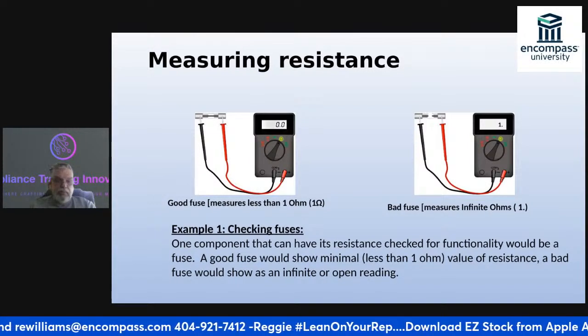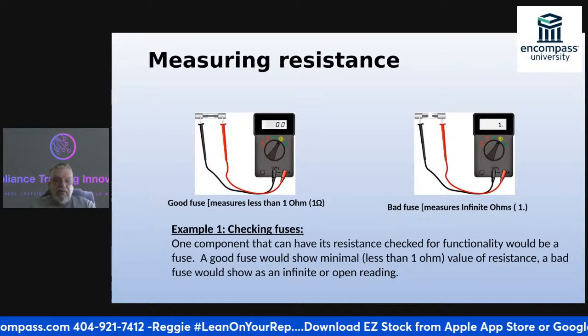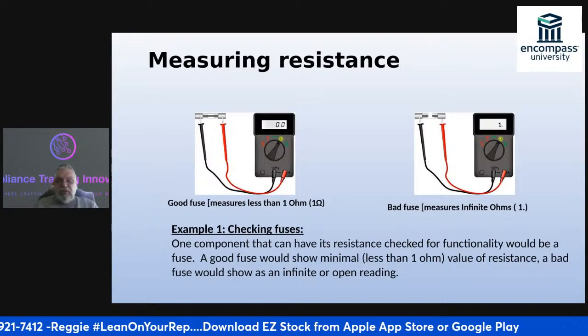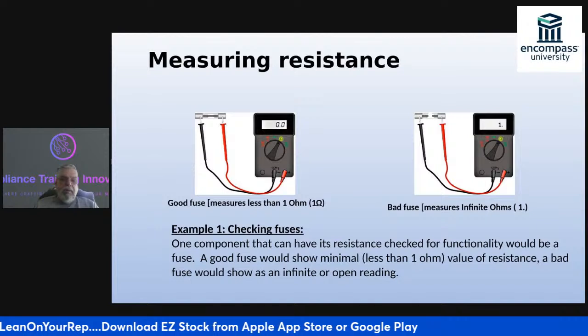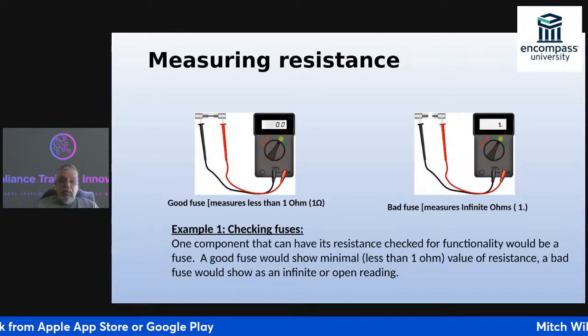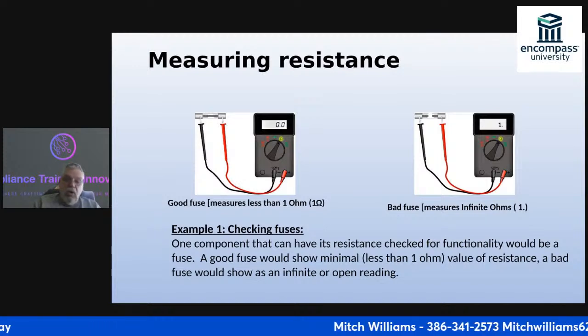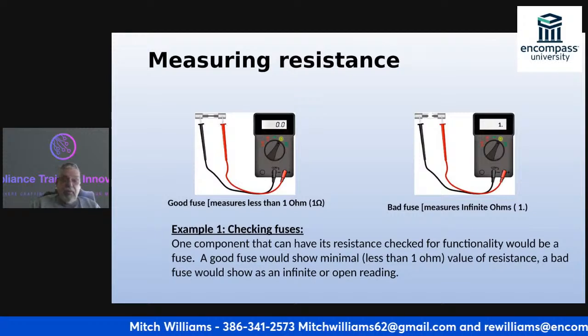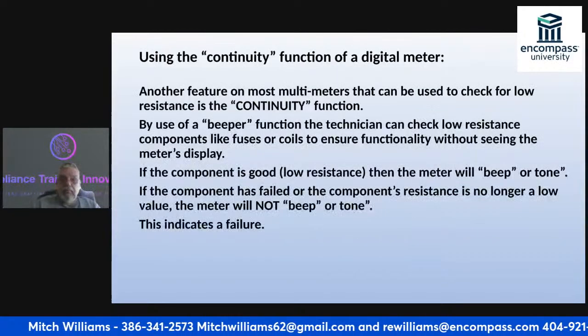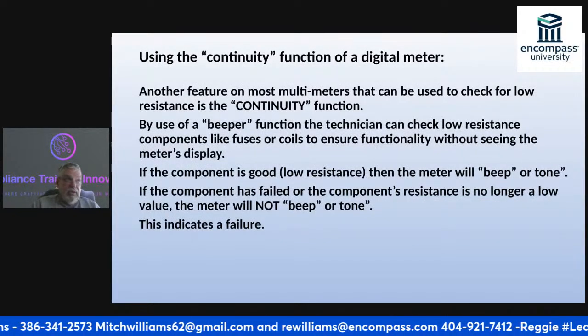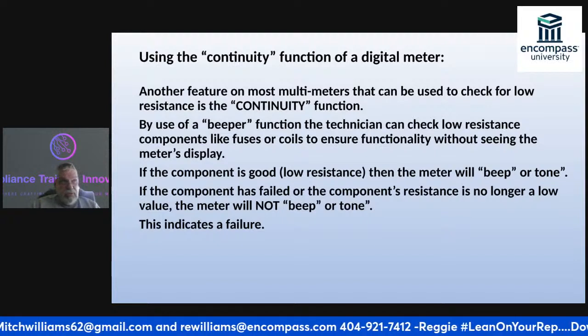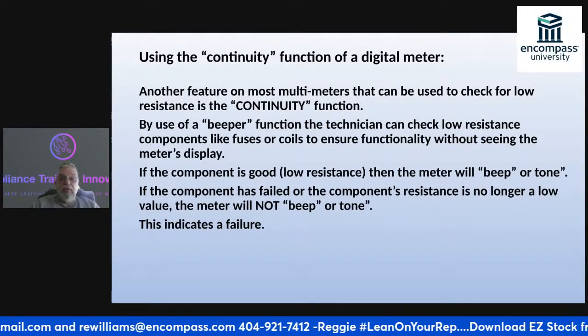The component that can have its resistance function for functionality would be a fuse. A good fuse would show a minimal, less than 1 ohm value of resistance. A bad fuse would show an infinite or open reading. Same thing if I'm checking a compressor. That's how I know if it's good. I can actually check a compressor with a continuity function.